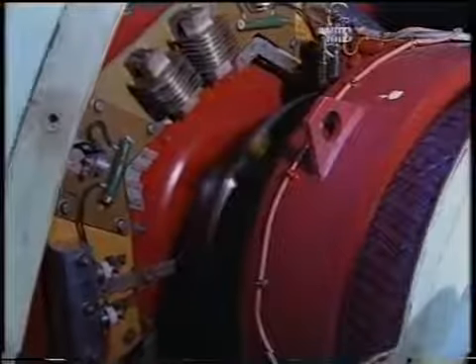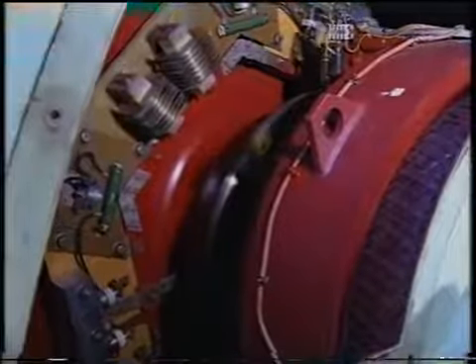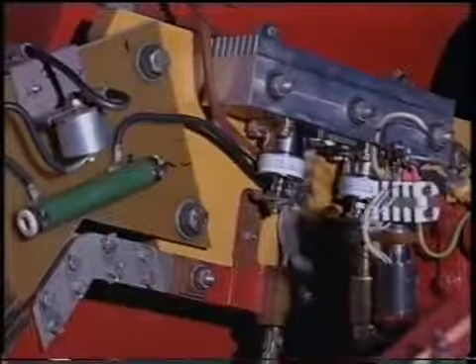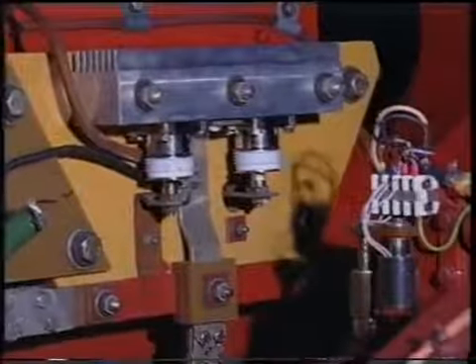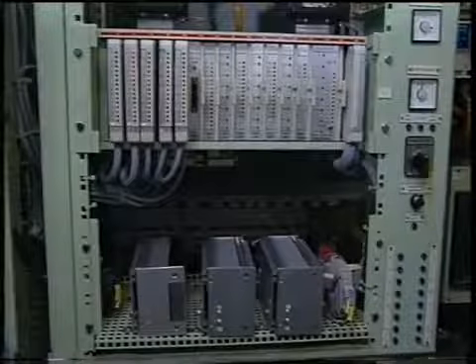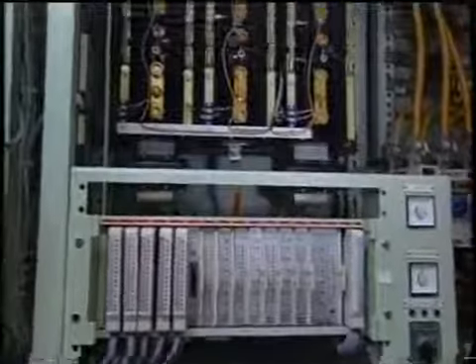A synchronous motor has field poles mounted on its shaft which lock into synchronism with the stator rotating magnetic field. The rotor field requires a DC current to magnetize each pole to the required strength to produce the shaft torque. The DC field current is obtained from a small shaft-mounted rotary AC exciter, also called a rotary transformer, which supplies shaft-mounted diodes. This is called brushless excitation, as no moving contacts are used. The AC supply to the exciter uses an AC-AC thyristor controller. There is a spare excitation unit which can be switched to replace either the port or starboard unit.